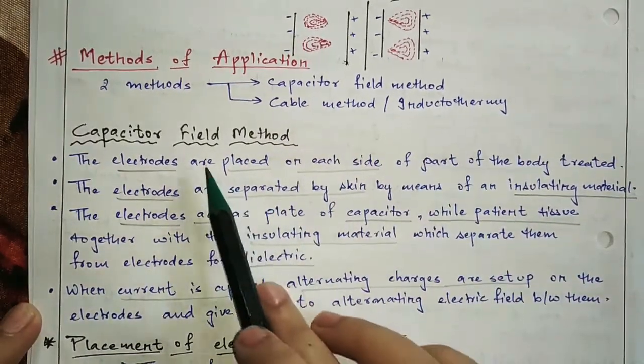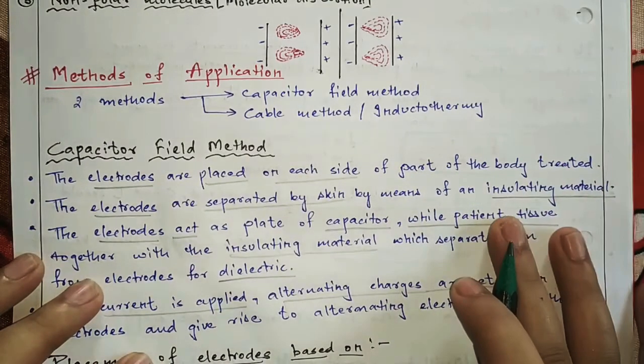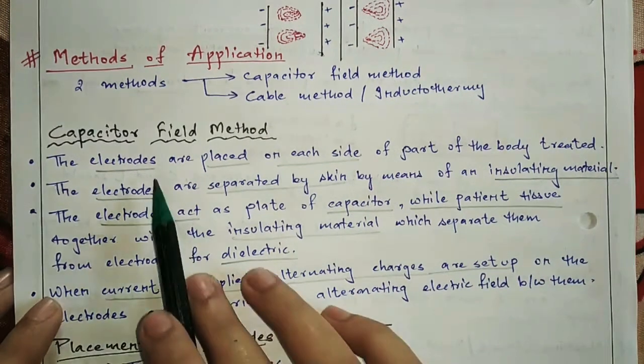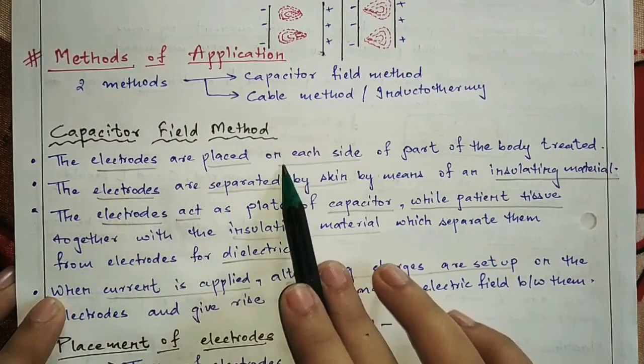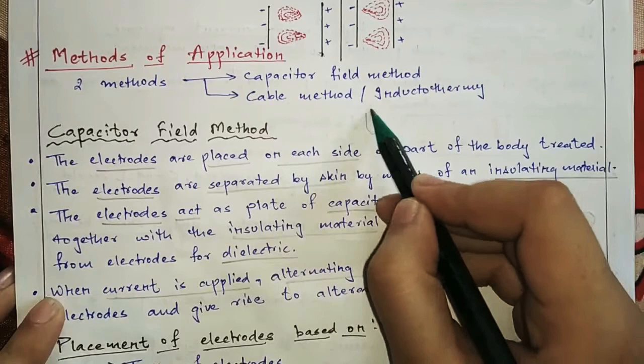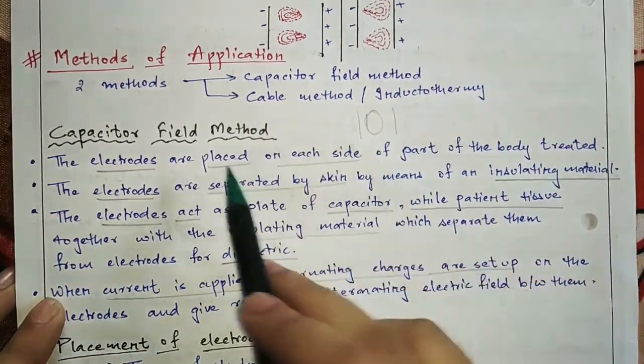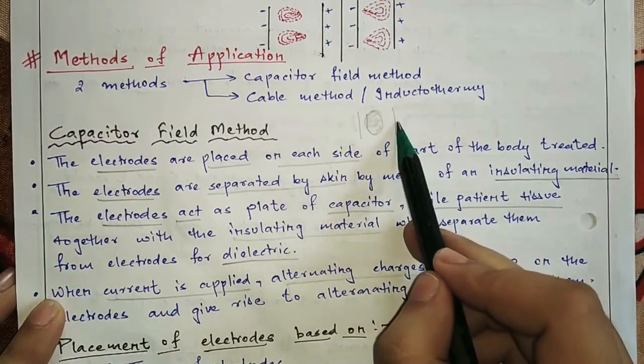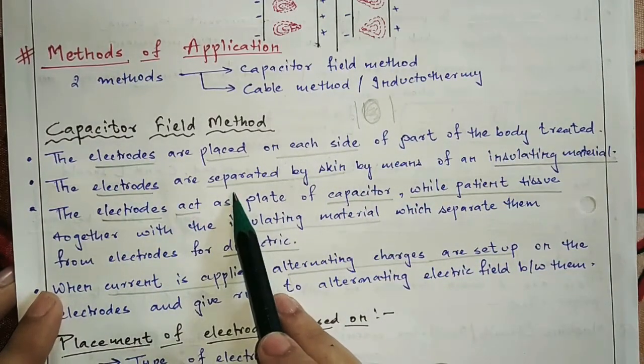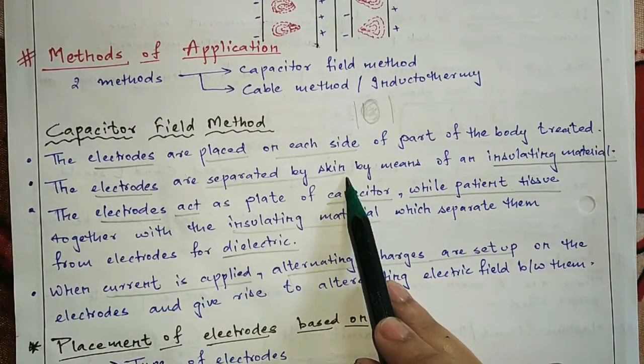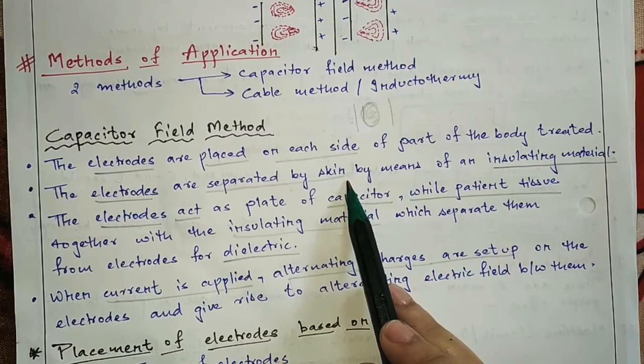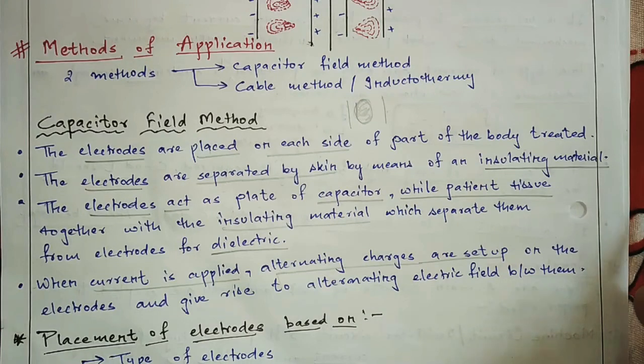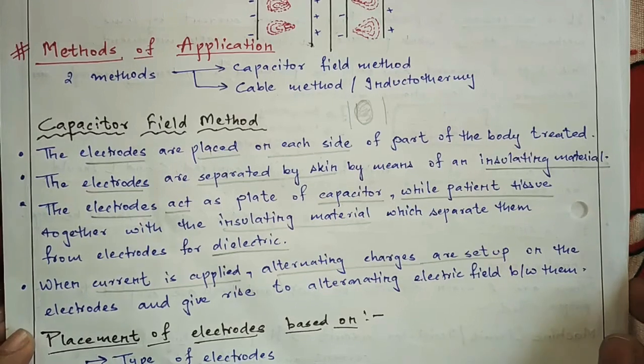Capacitor field method. The electrode that we use in SWD, we understand it as a plate of a capacitor. The electrode — as we are calling it — is placed on each side of the part to be treated. This electrode is not in direct contact with the skin; it is separated by an insulating material. The insulating material can be a roll of bed sheet or any clothing that works as an insulating material.